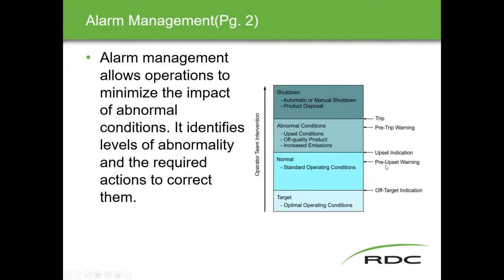If the alarm system is designed properly, we can use it as a good tool to help facilitate management of alarms. Between target and normal, there's an off-target indication. Moving up: a pre-upset warning, then an upset indication entering the abnormal zone, then a pre-trip area, and finally a trip — which we want to avoid at all costs. Not every operating station will show an alarm for every one of these conditions, but these are things considered when the alarm philosophy is designed.